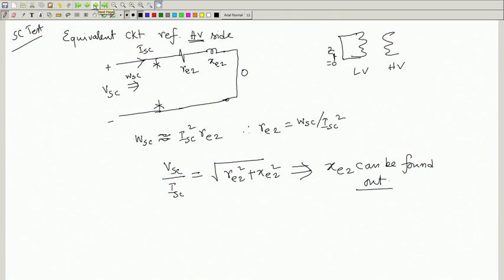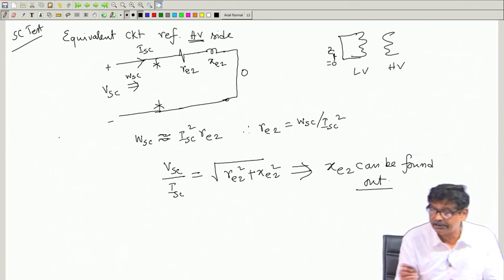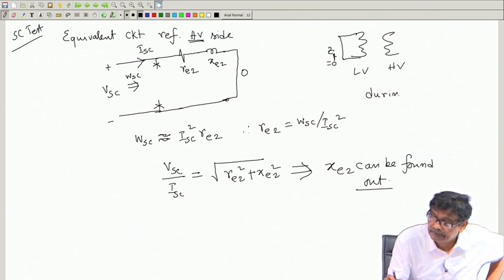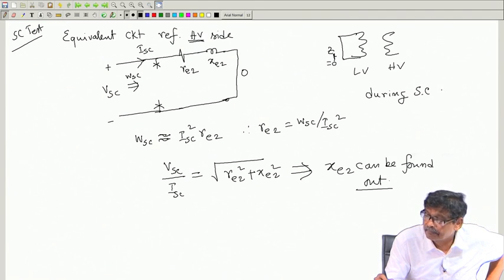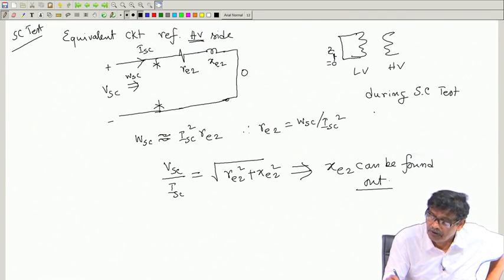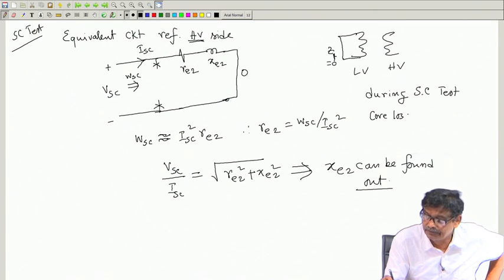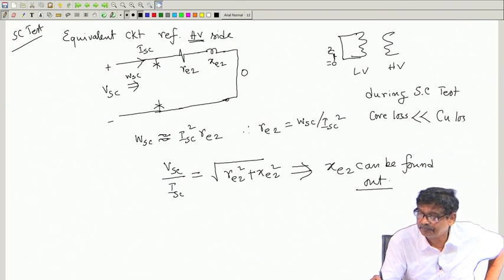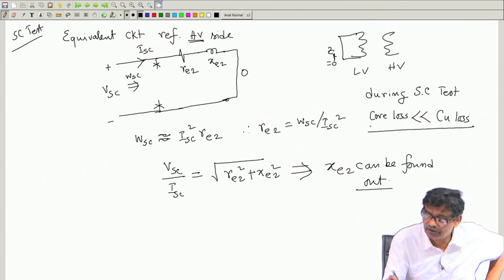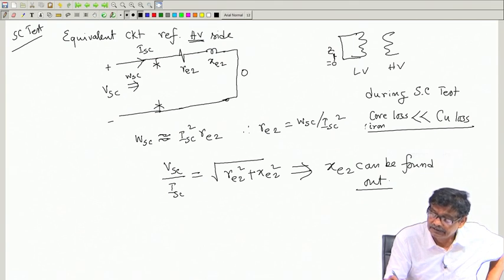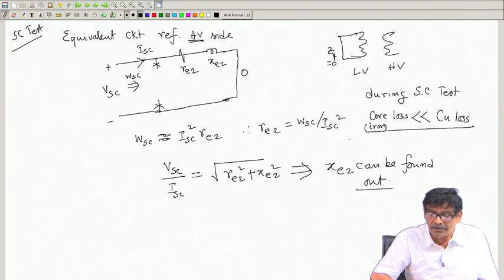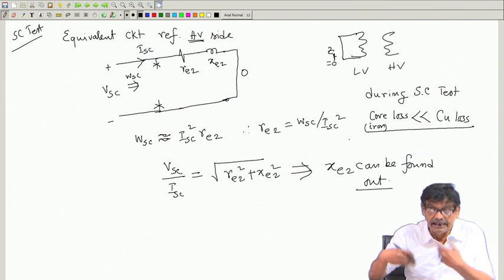During the short circuit test, the wattmeter reading approximately records the copper loss. Core loss can be neglected during the SC test — core loss, also called iron loss, is much, much smaller than copper loss, so it can be neglected. We say the wattmeter reads copper loss only.